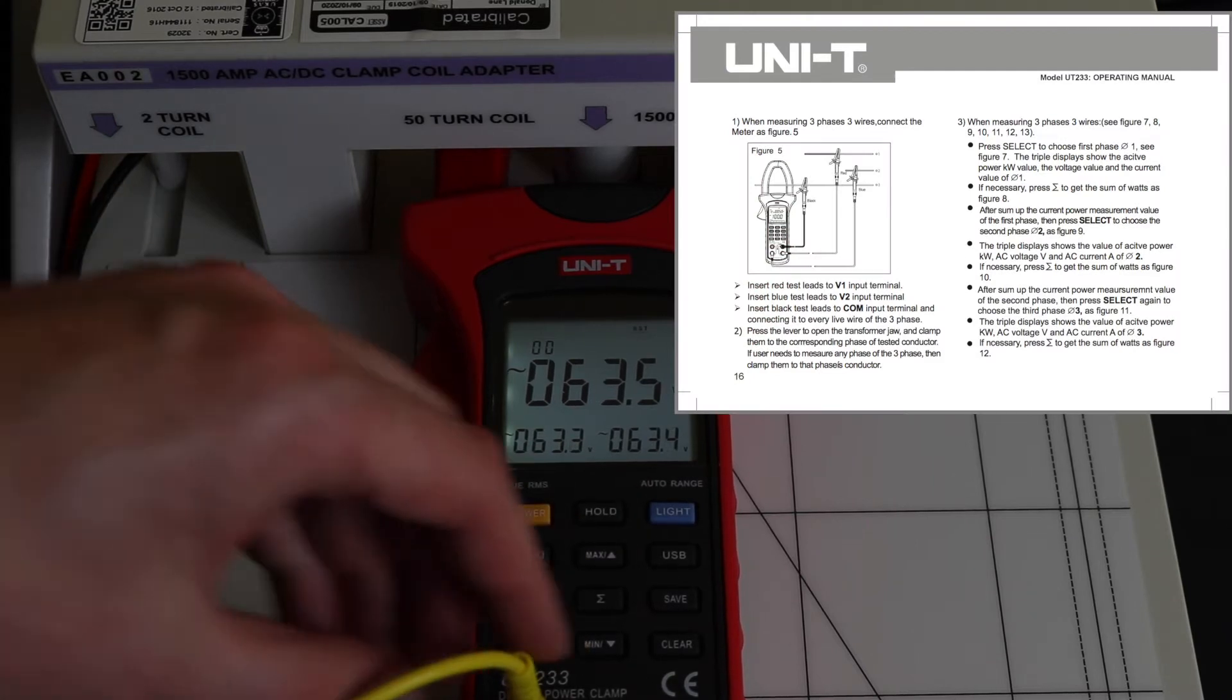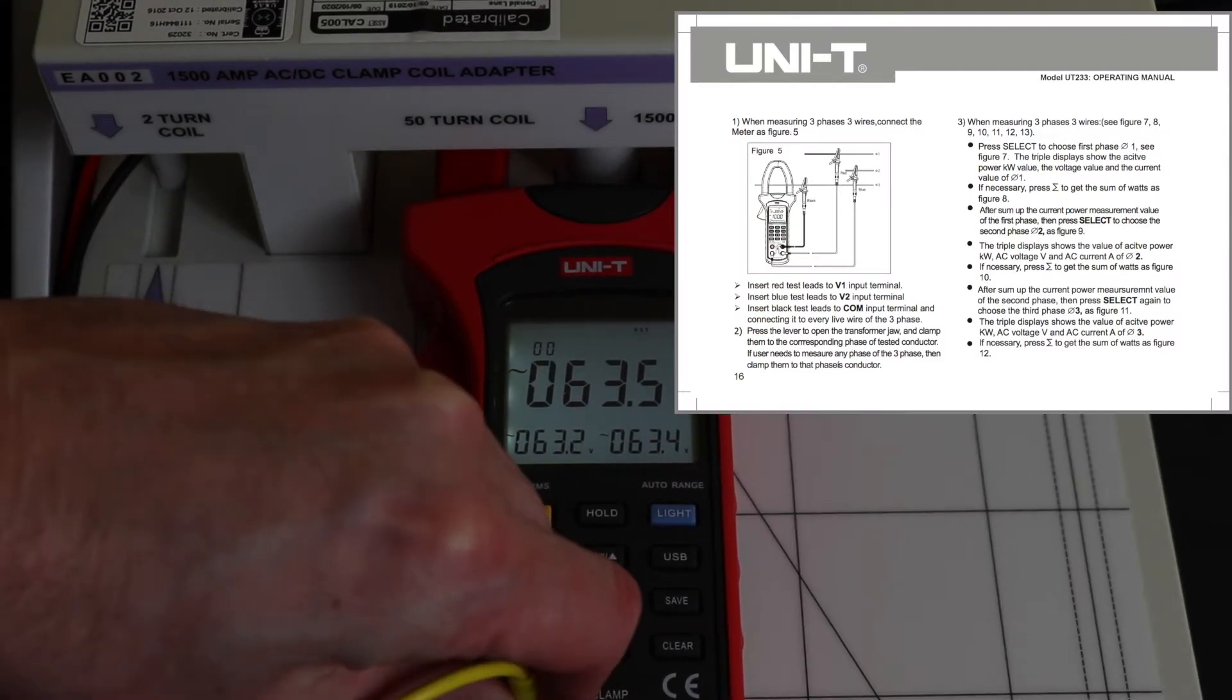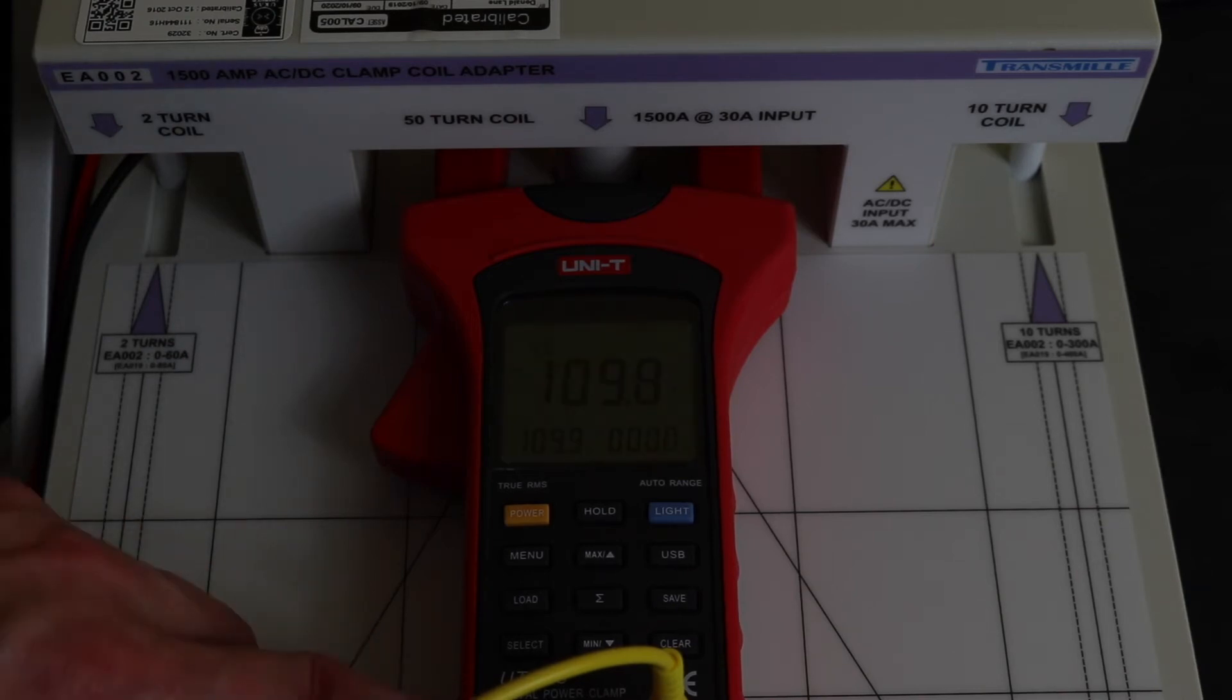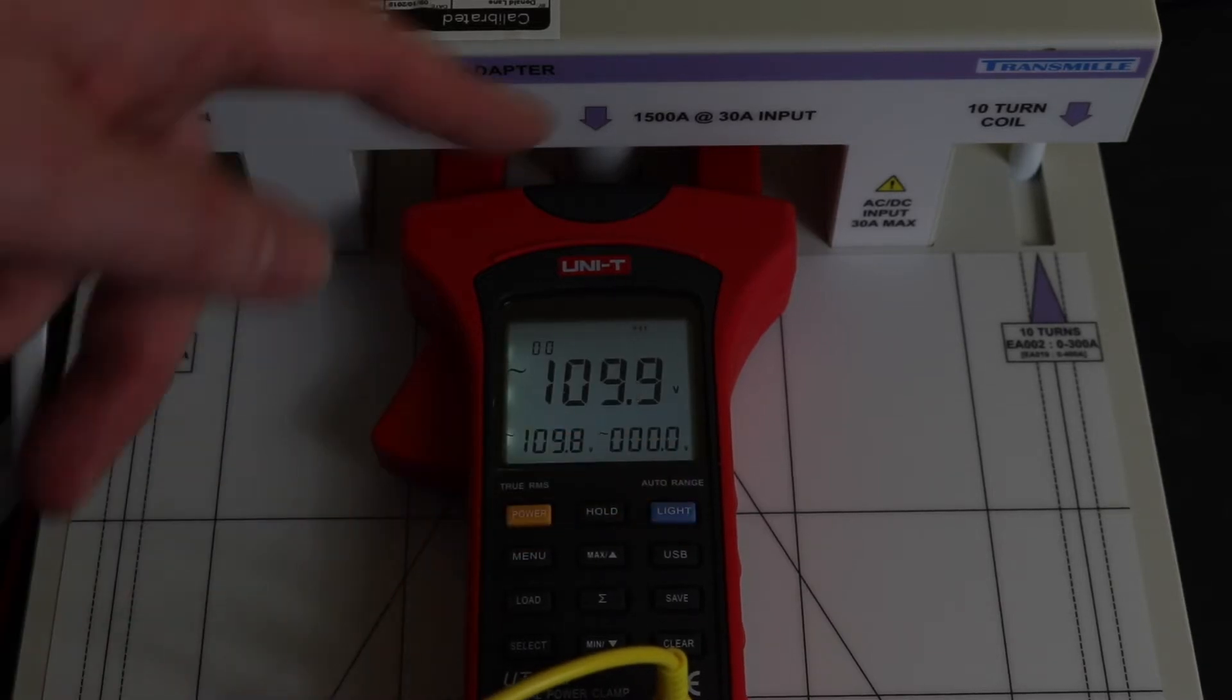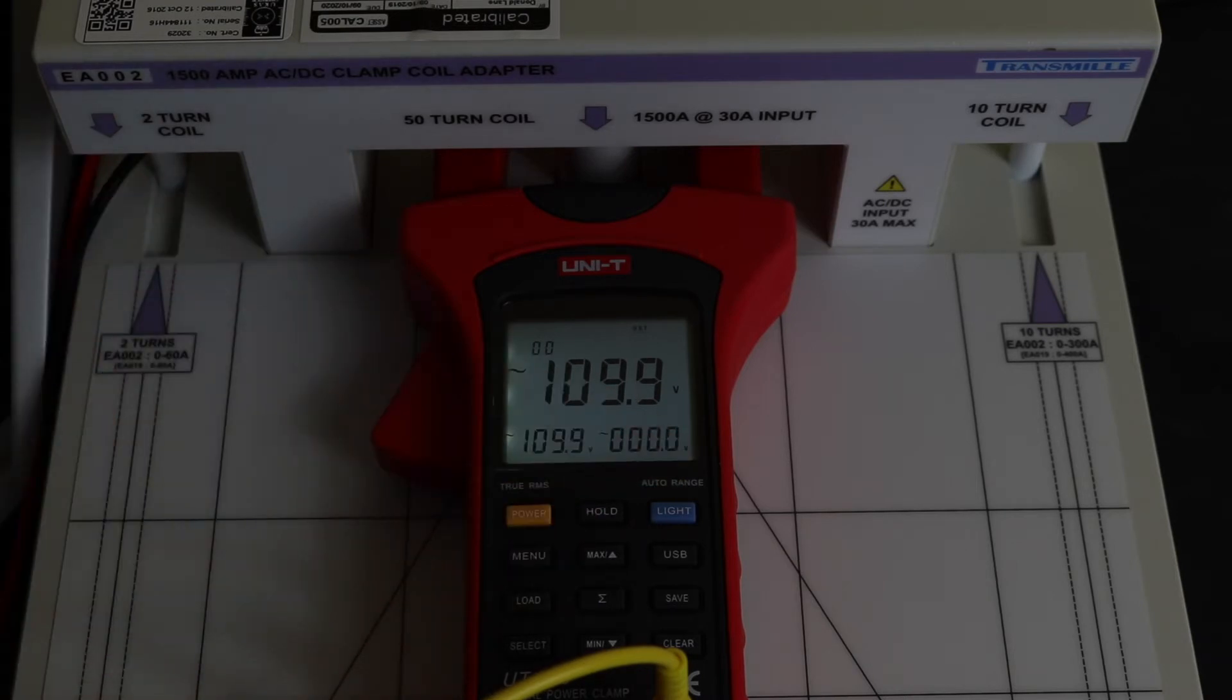this up - it's not very clear at all, but it seems like you're supposed to have three-phase 3-wire connected up with phase 3 in the common and the V3 empty. If I do that, you can see I've got the phase-to-phase voltage there: 110 to 110, and the V3 is missing. Yeah, it's a bit of a bizarre setup. I'll go through each of those.